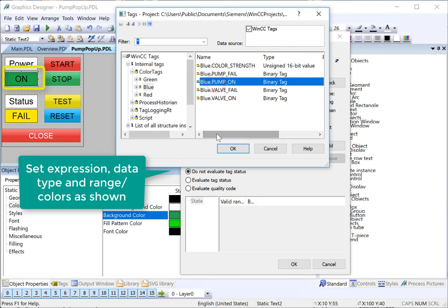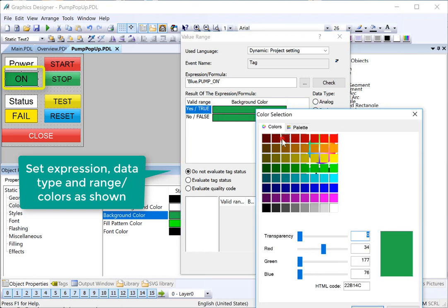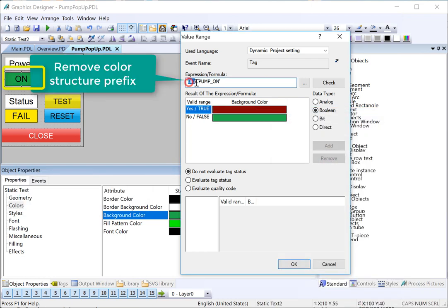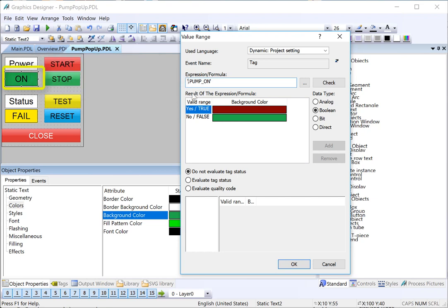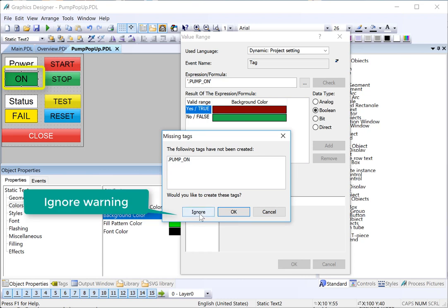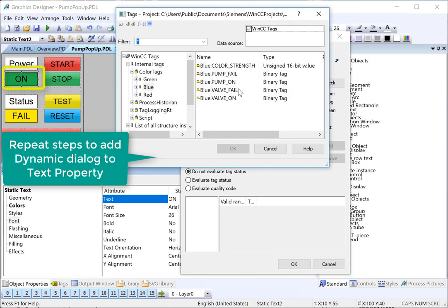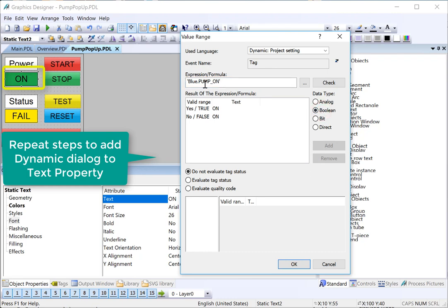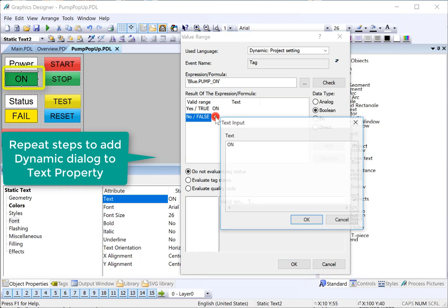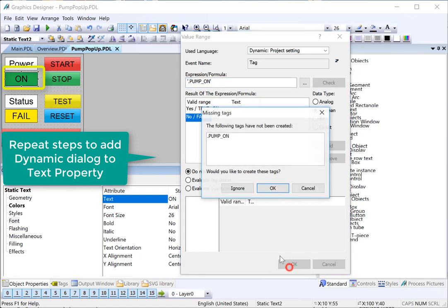This is going to be our pump on. We'll add a Boolean expression — if the pump is on, background color is red; if this is off, it's green. We're going to get rid of the prefix and only use the member name, which starts with a dot. So in this case, dot pump on. When we click OK, it's going to say the tag doesn't exist — you're just going to click ignore. We'll do the same thing for the text: choose dynamic dialog, grab any pump on tag, set it to Boolean. If the tag is true, the text will be on; if it's false, it will be off. Then get rid of the tag prefix, click OK and ignore.